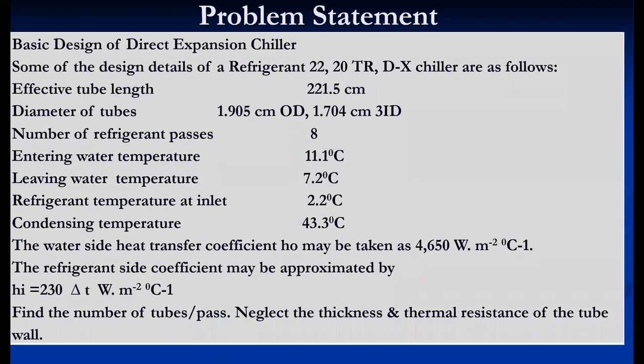For this topic we focus on DX type evaporators. We go directly to the problem statement: this is a basic design of a direct expansion chiller. Some design details are given — a 20 TR DX chiller. Effective tube length is given, diameter of tubes inner and outer side is given. In a DX type evaporator, refrigerant flows through the tubes and water, which is to be cooled, flows through the shell.